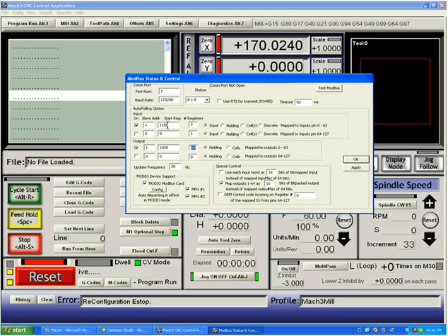The only thing you need to know is your start address register for both input and output. The update frequency here tells the system how often to send these packets to the Mod I/O and to read from the Mod I/O or any ModBus device. Typically, I set mine to 20 Hertz, so 20 times a second you will get data from the ModBus and send it to it.